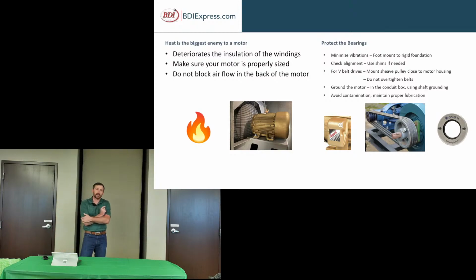Heat is going to be your biggest enemy, which also plays with lubrication because lubrication helps keep your bearings cooler. But heat is going to deteriorate the windings in your motor. You also want to make sure your motor is sized properly. If your motor is undersized, it's going to be working a lot harder and cause failures because it can't keep up with what you're trying to do. On the back of motors, you're going to see a little cover that goes over the back end. Do not cover that. Try and keep it clean. That is there for a reason. There's a fan in there running air over the motor itself to keep that heat down, which in the end protects your equipment.